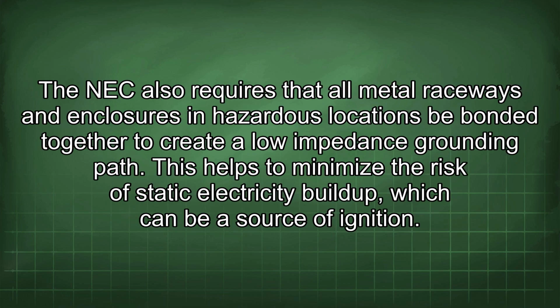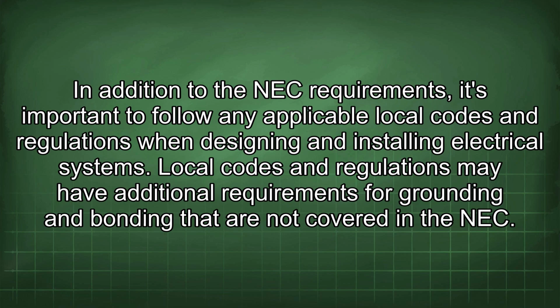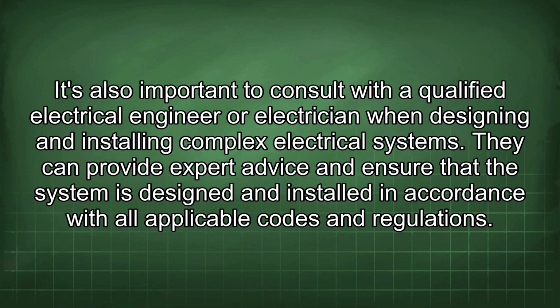The NEC also requires that all metal raceways and enclosures in hazardous locations be bonded together to create a low impedance grounding path. This helps to minimize the risk of static electricity buildup, which can be a source of ignition. In addition to the NEC requirements, it's important to follow any applicable local codes and regulations when designing and installing electrical systems. Local codes and regulations may have additional requirements for grounding and bonding that are not covered in the NEC. It's also important to consult with a qualified electrical engineer or electrician when designing and installing complex electrical systems. They can provide expert advice and ensure that the system is designed and installed in accordance with all applicable codes and regulations.